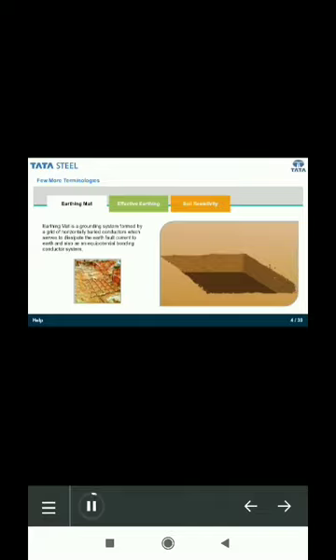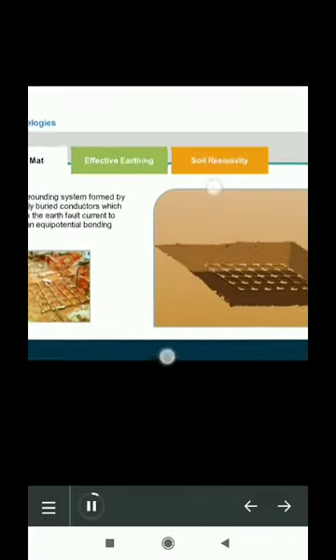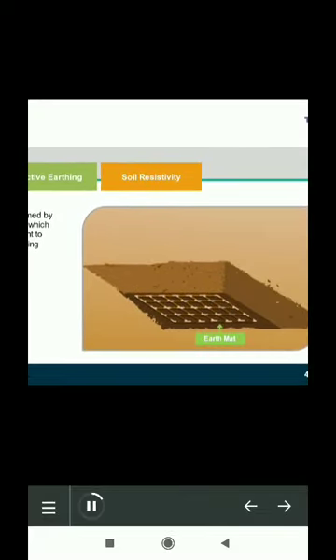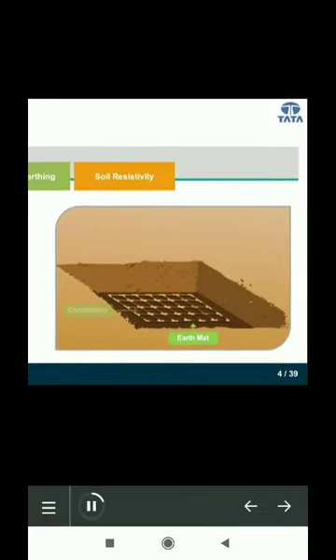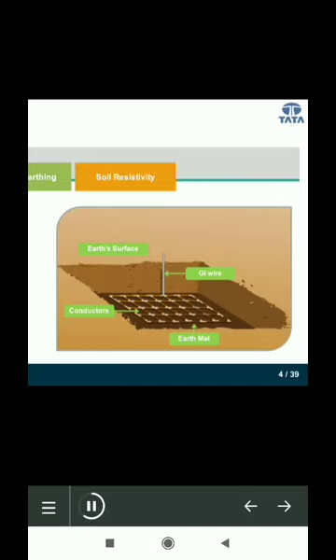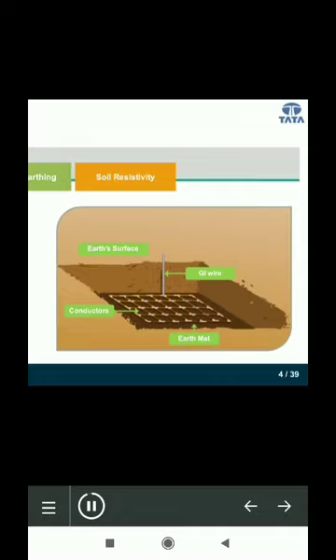Earthing mat is a grounding system formed by a grid of horizontally buried conductors which serves to dissipate the earth fault current to earth and also as an equipotential bonding conductor system. As you can see, the grid has conductors and the galvanized iron wire, or GI wire, connects the mat to the installation above the earth's surface. This is what an earthing mat looks like.